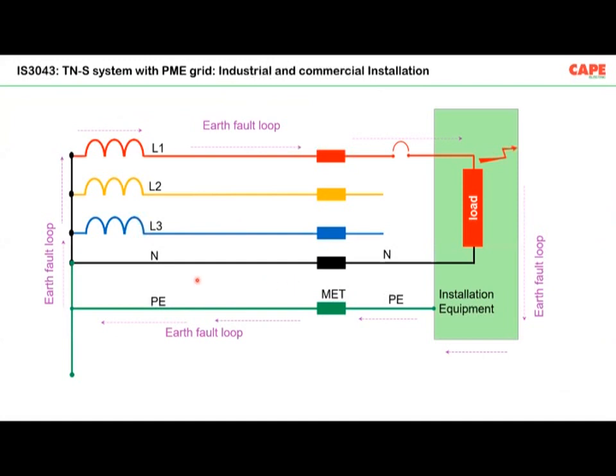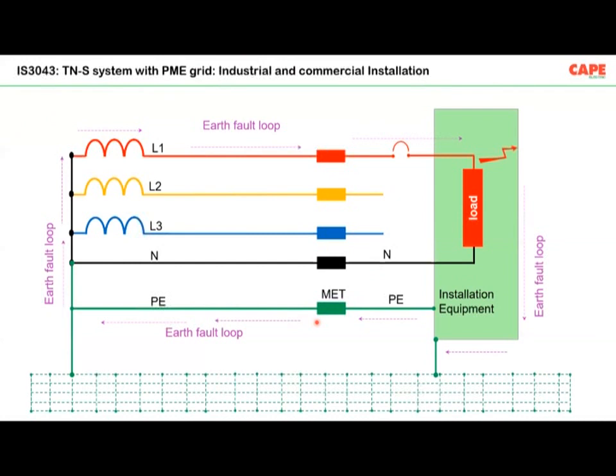Now, IS 3043 recommends a system called TNS for industrial and commercial premises with PME. What is PME? In large installations, you are sometimes unable to create a very low fault loop impedance path. As a result, your protective device may not work. In order to solve the problem, you make an earth grid and interconnect the neutral of the system and the exposed and extraneous conductive parts of the installation, so that you have an additional path for the fault current to flow back to the source. So automatically the fault loop impedance is smaller and you get efficient disconnection of the supply. And this is what is explained in IS 3043.